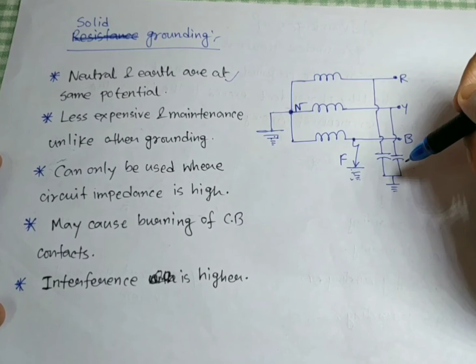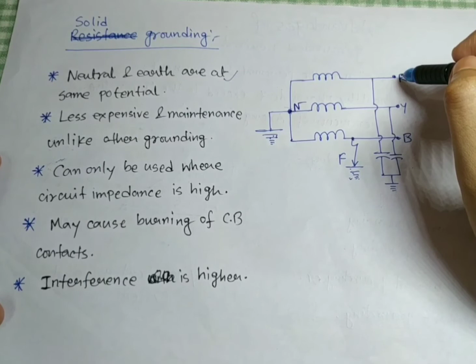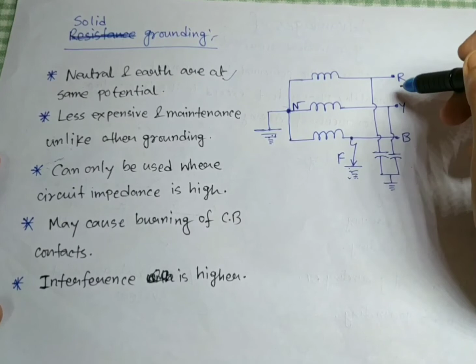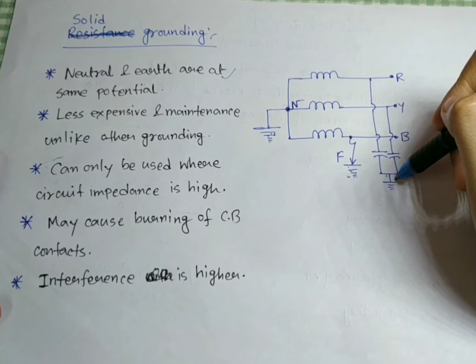Another advantage is the moment your phase B is connected to the ground. In case of ungrounded neutral, during the arcing ground phenomena there is a chance that the healthy phases, and not only the healthy phases but also the faulty phase, will experience a very high amount of voltage. But here this phenomenon will not occur. Why? Because there is a capacitance effect between the healthy phases and the ground. Now the neutral is also grounded, so these 2 points are almost the same.